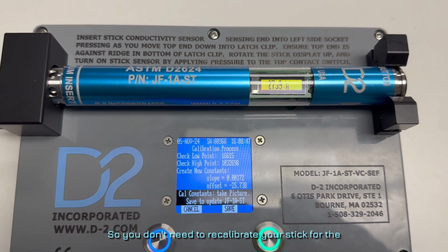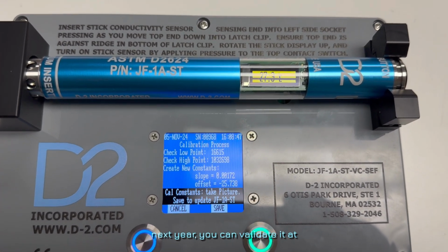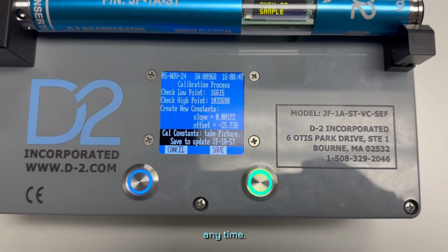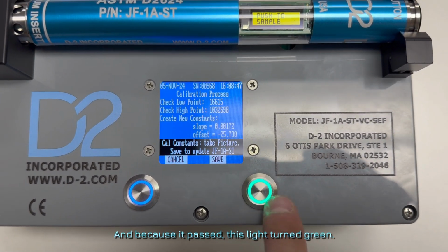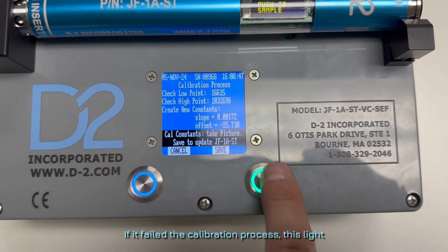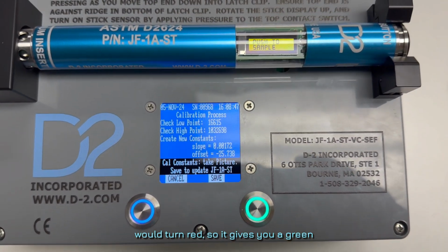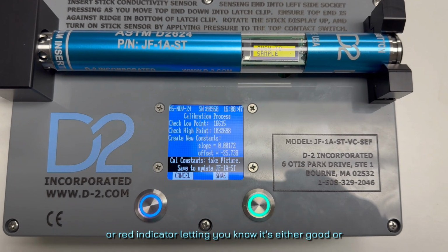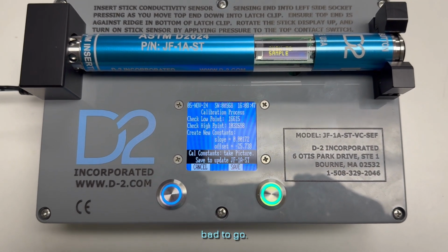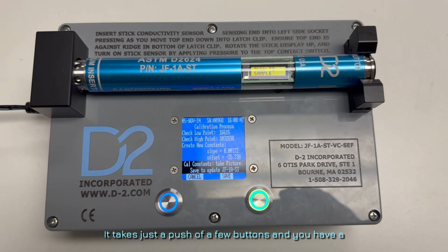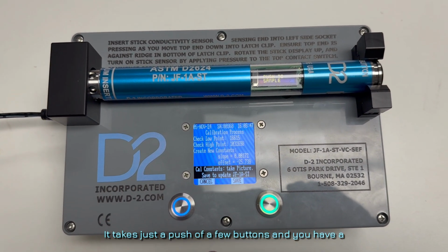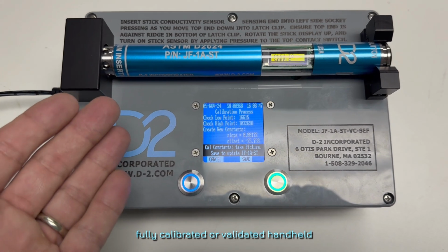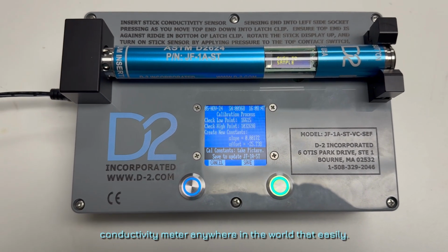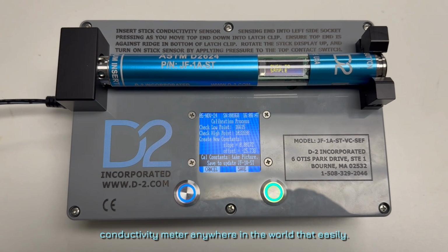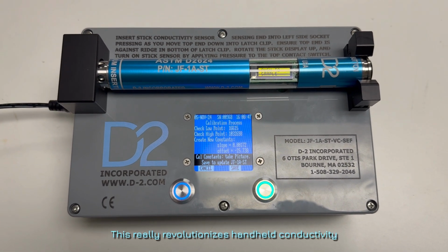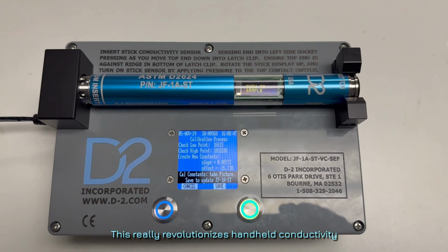So you don't need to recalibrate your stick for the next year. You can validate it at any time. And because it passed, this light turned green. If it failed the calibration process, this light would turn red. So it gives you a green or red indicator letting you know it's either good or bad to go. So there you go. That's how easy it is. It takes just a push of a few buttons and you have a fully calibrated or validated handheld conductivity meter anywhere in the world that easily. This really revolutionizes handheld conductivity measurement.